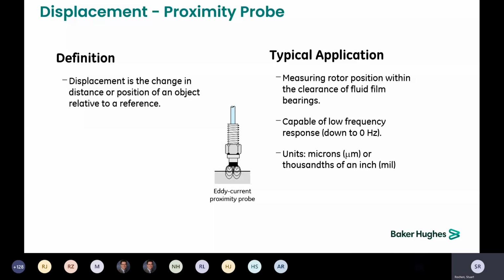So we're going to start with proximity probes. Proximity probes measure displacement. Generally used with fluid film bearings. It is capable of going down to low frequency, actually 0 hertz, because things that aren't moving, or not rotating, can be measured for displacement. Things like case expansion, thrust, differential expansion, things like that that do not require rotation gets down to the 0 hertz. And it's generally reported here in the States in thousandths of an inch or mils, and in other parts of the world they use microns.